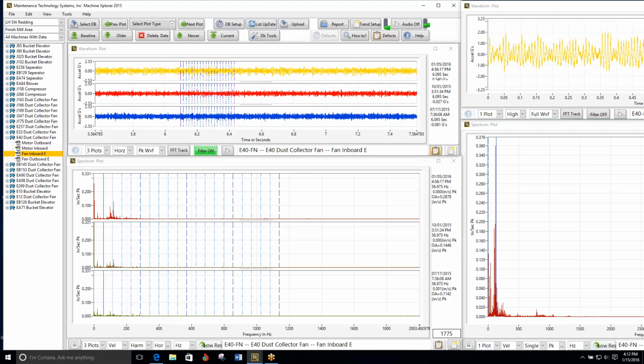I'm not going to have the benefit of historical data on this stuff Scott's sending me. Yeah, but down the road you will. So you just end up setting those up as single plots initially. You have to do a little more analysis when you just have a single data plot, because if the vibration's not changing, then it becomes a who cares.